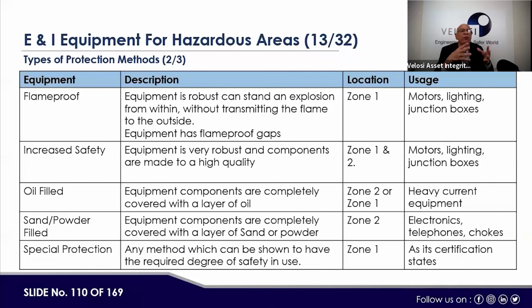Then flameproof means what? The equipment can withstand an explosion from within without transmitting the flame to the outside. The equipment has a flameproof gap, for zone 1. Motors, lighting, and junction boxes are applicable. Then increased safety. If we have to say the protection level, the equipment is very robust and the components are made to a high quality, for zone 1 and zone 2. It also covers motors, lighting, and junction boxes.